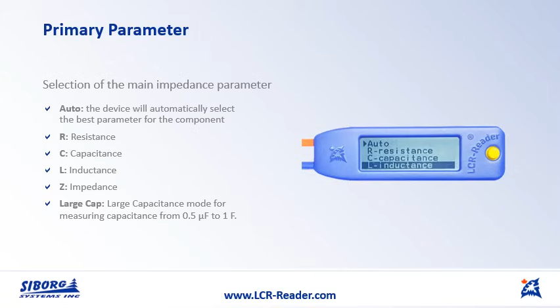Large cap mode. This mode is activated by using the primary parameter large cap item in the parameter setting menu and has two sub modes: large cap from 0.5 to 40 millifarads and super cap from 40 millifarads to 1 farad. So by manipulating the joystick you can toggle between the two modes, and all the parameters are displayed on the screen.